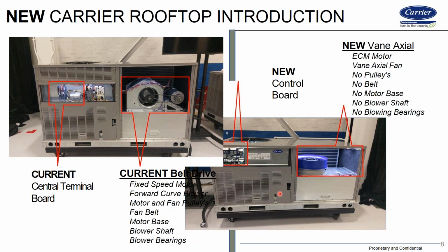The other thing we see, and this isn't necessarily new to this unit, this problem's been around for a long time. We deal with it all the time with belt drive units as well, and that's strip malls. What typically is in a strip mall is you've got supply grills in the ceiling and return grills in the ceiling, usually just a couple of ceiling tiles away from one another. So you've got early morning occupancy after it's been unoccupied all night, and now we've got to regain say 4, 5, 6 degrees of space temperature. This thing runs and runs and runs, and we're taking discharge air that may be heated to 120 degrees and throwing it along the ceiling right back into the return, because of stratification and the throw of the supplies and their proximity to the return.